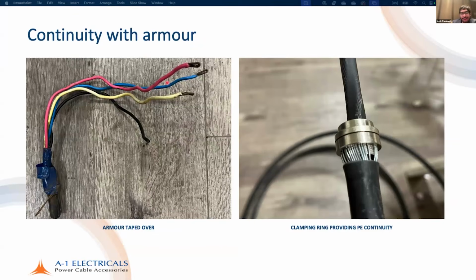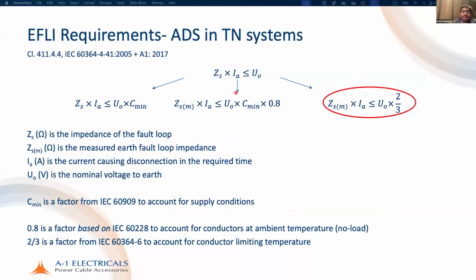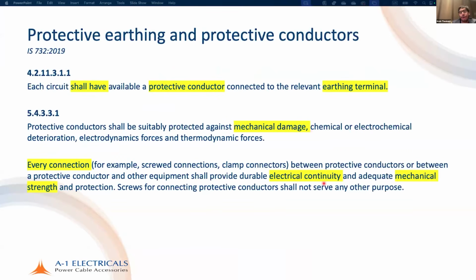Unfortunately, we forget that resistance, this is just on paper. To actually achieve this requirement, we need proper electrical continuity, not just for live conductors, also for our protective conductors. And the most common protective conductor that is there everywhere, but it's not being correctly used, is the armor. So you can see here, this is the armor. The armor has just been taped over, and somebody has pulled out a steel wire. Completely inadequate arrangement that we have here.